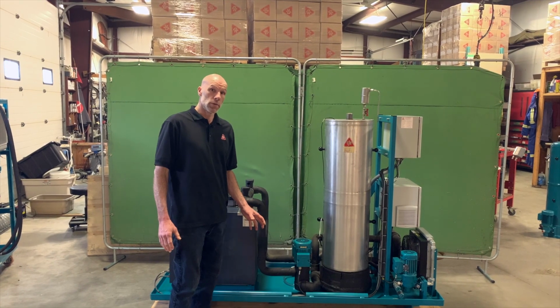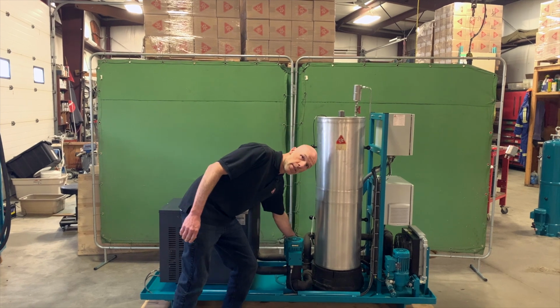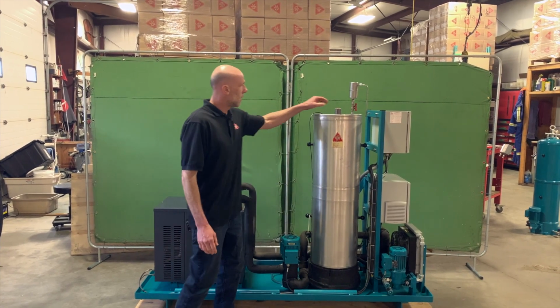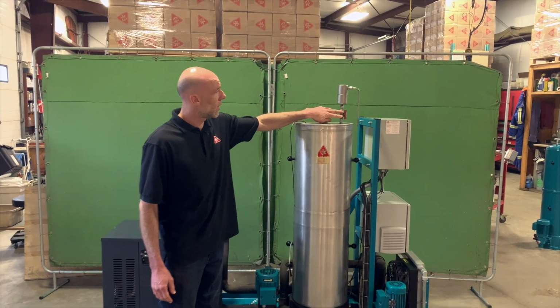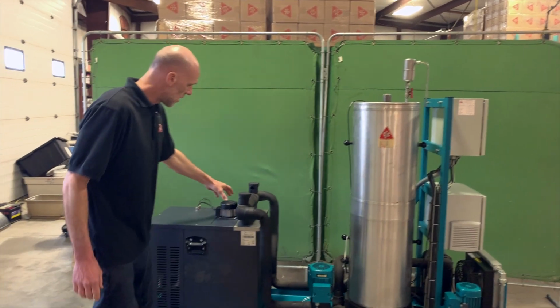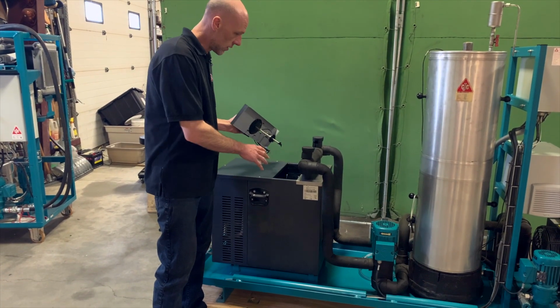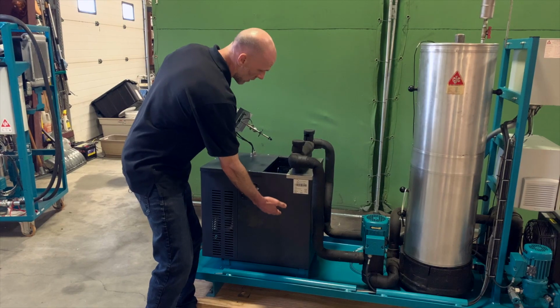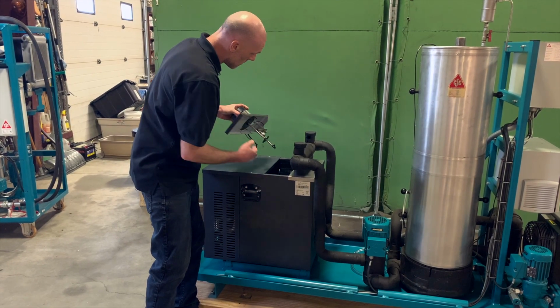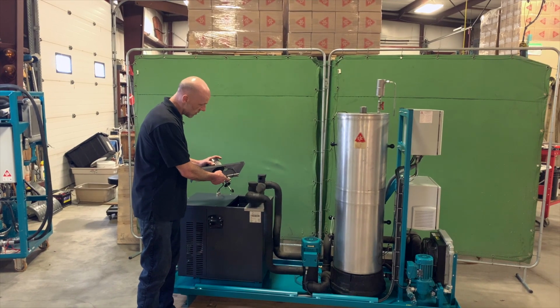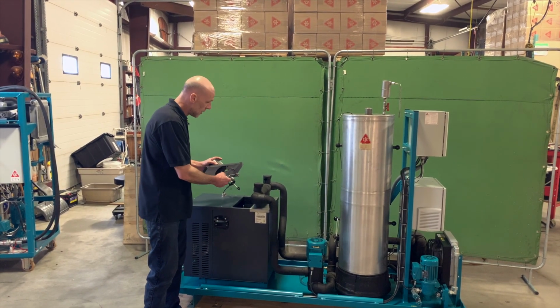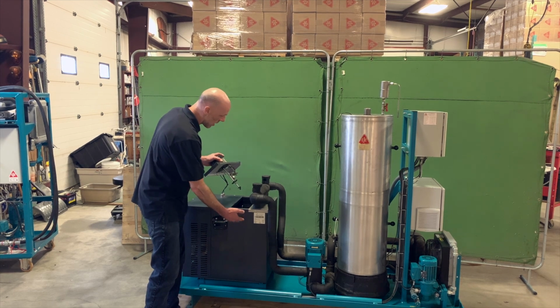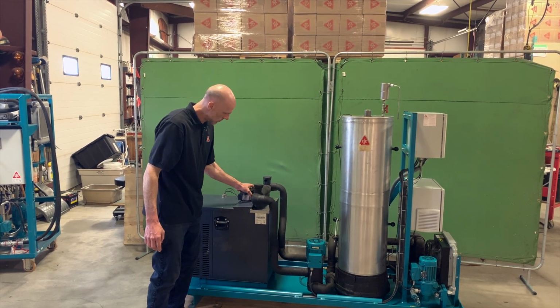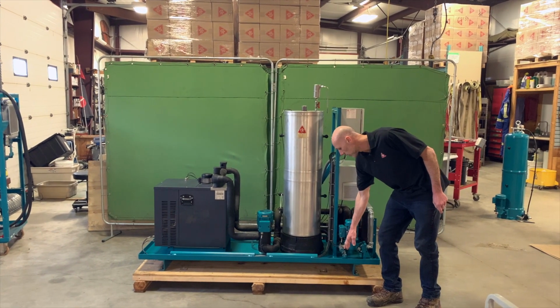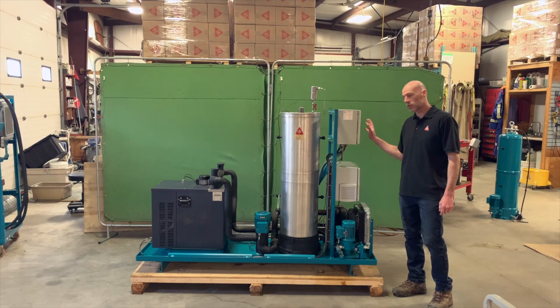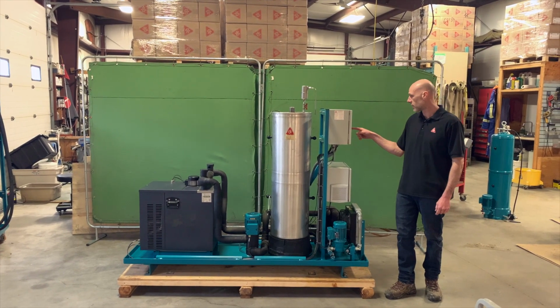There's a couple things you want to check before you start up the unit. The first is that the drain valve on the bottom of the filter housing is closed. Next, you want to make sure that the valve, if you have it on the auto air vent, is open. And then you want to make sure that you've got water in the chiller assembly. So this is a water bath chiller, so you'll need to make sure that there's always a volume of water in here. There is a float switch inside here, so if the water level is too low, it will let you know on the panel. And there's also a spillover pipe when you fill the water level up high enough so that you'll know that you've got the right level. Make sure that if you have valves on your inlet and outlet, that those are open, and then you're ready to start the unit. You can do that by pressing the green button on the front of the panel.